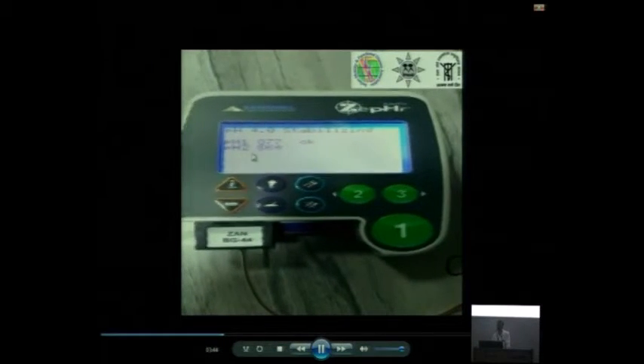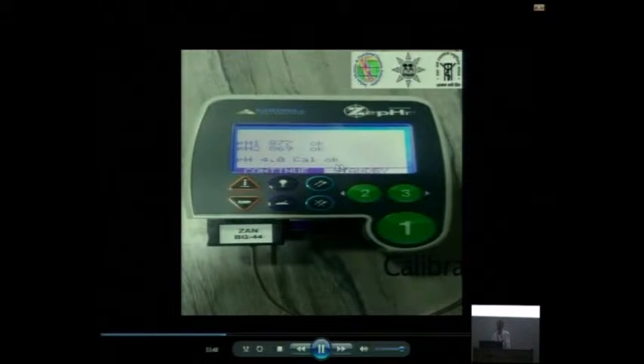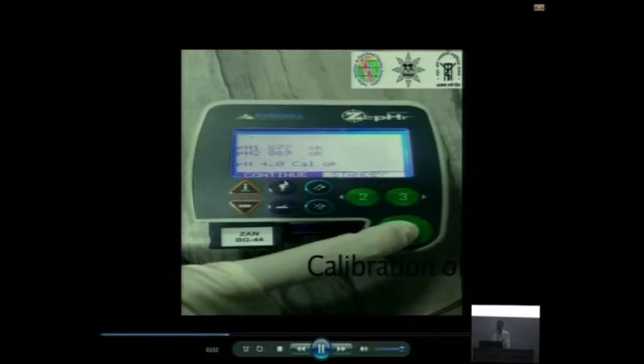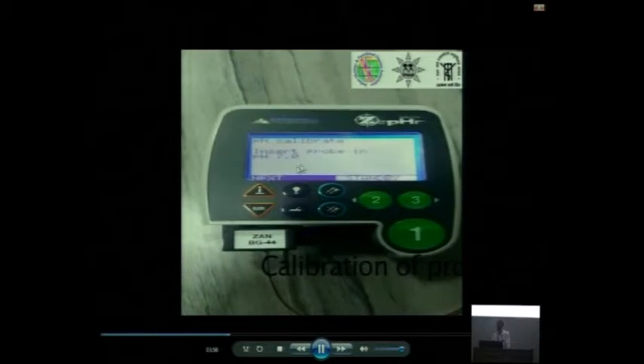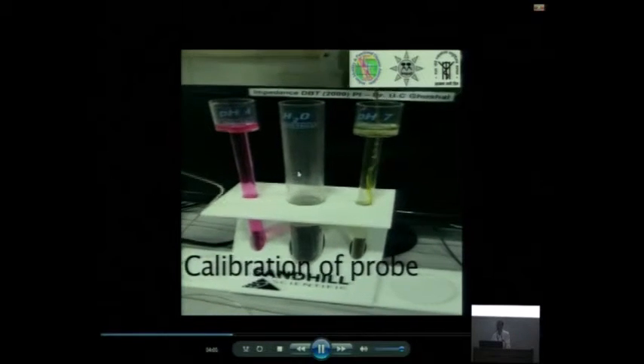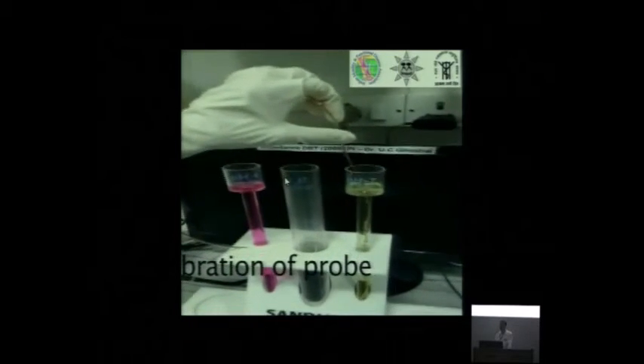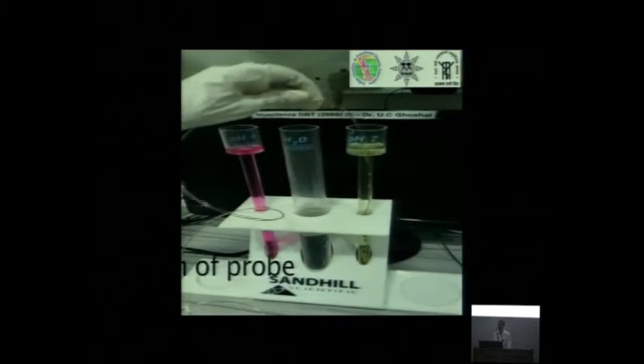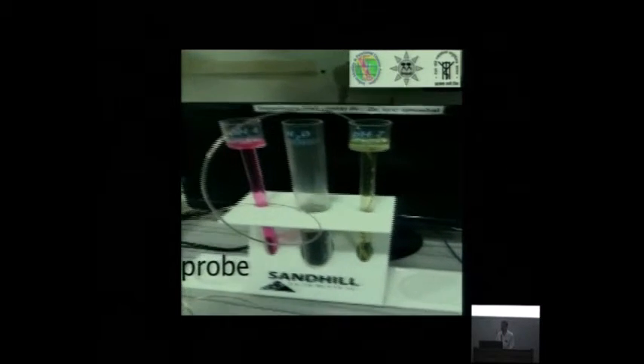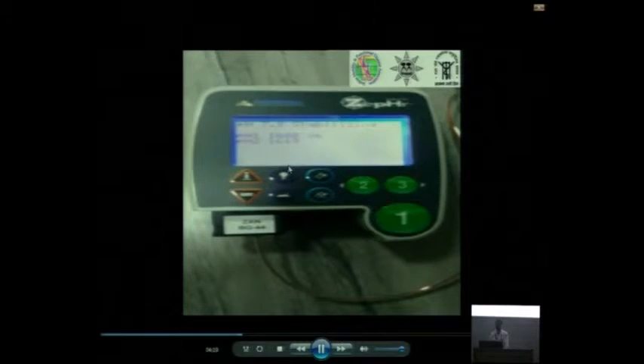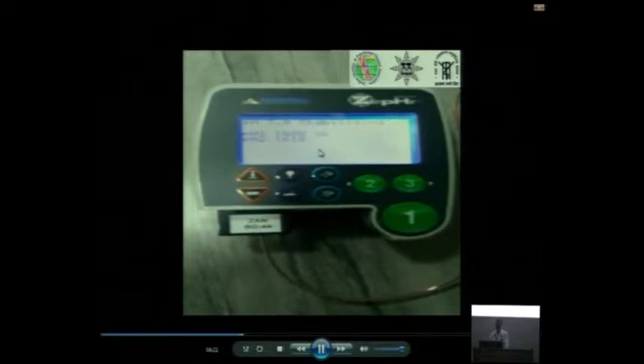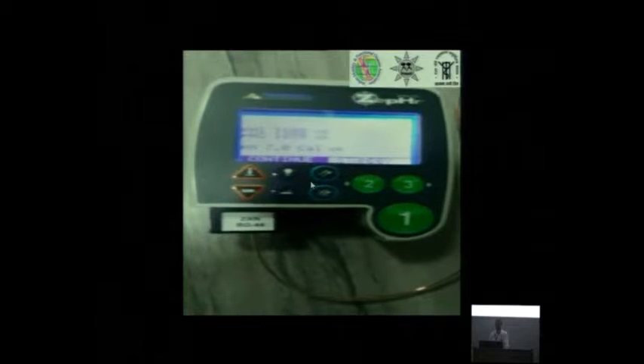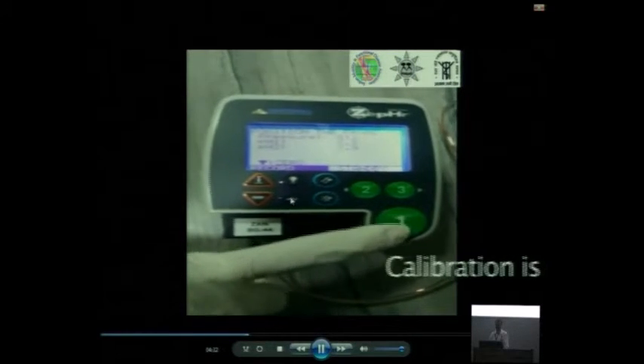Now we have to do pH4 calibration. Continue. Insert probe in pH7. Typically we wash this probe in water, wipe it off, and then put in pH7. Don't go directly from pH4 to pH7. In between put it in water so that you clean that pH4 solution. Now it says this is again reading the pH7. It says pH1, that is port number 1, is okay. It has already read what is port number 1. pH7 calibration okay. Continue.